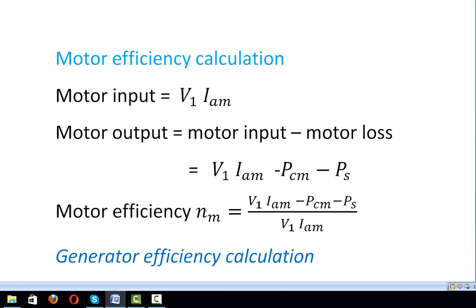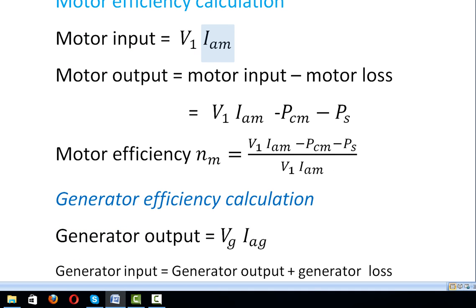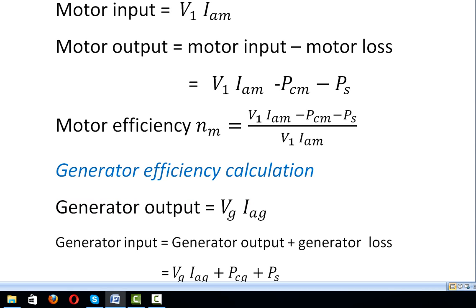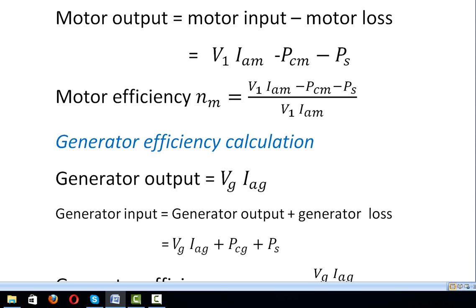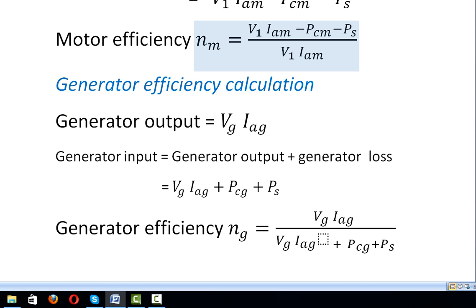Motor efficiency calculation: motor input equals V1 × IAM, where IAM is the series motor armature current equal to rated current. Motor output equals motor input minus motor losses, that is V1 × IAM minus motor copper loss PCM minus motor stray loss PS. Motor efficiency η equals motor output divided by motor input, that is (V1 × IAM minus PCM minus PS) divided by (V1 × IAM).